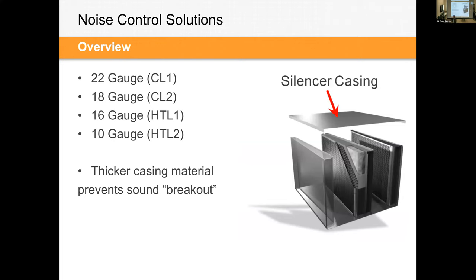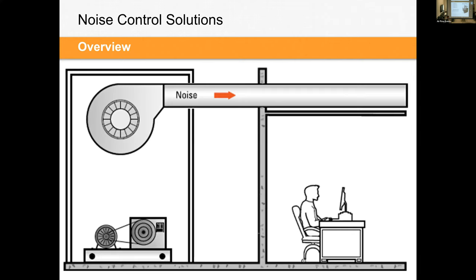Another thing you can change, and this is often misunderstood, is that the casing exterior gauge can be increased. We call this the class of silencer: class one, class two, high transmission loss two. The idea is that the thicker the casing, the better the silencer will contain and prevent sound from breaking out into the area where it's installed. What I mean by that, and this depiction does a good job of explaining it, is that when you have noise within a duct system, that sound energy is typically going to transmit through the duct down into wherever it's leading to, whether it's the supply or the return.